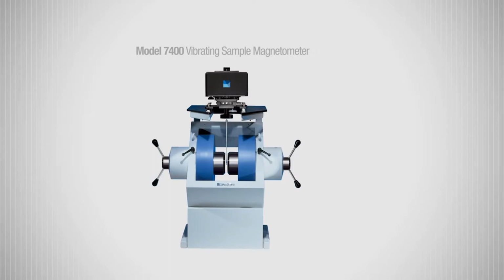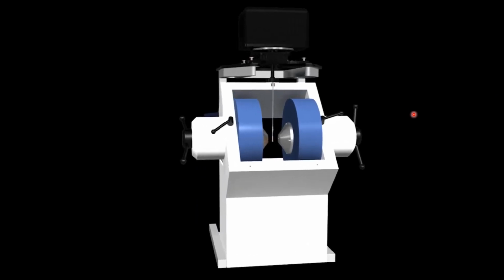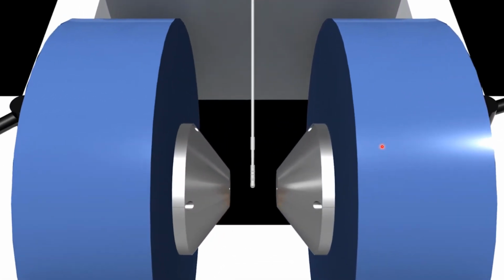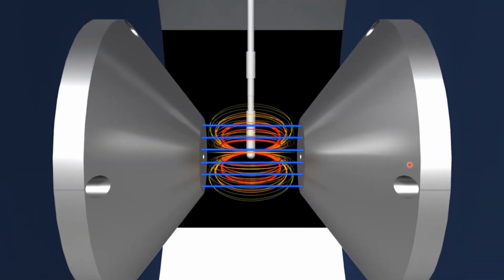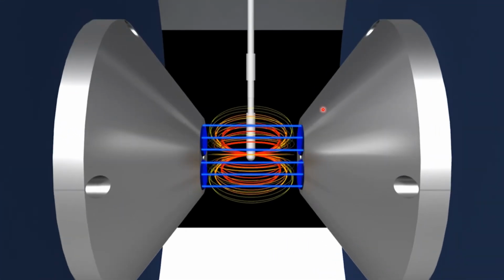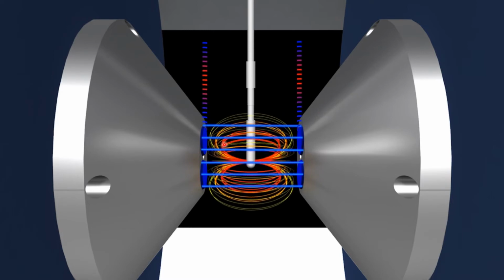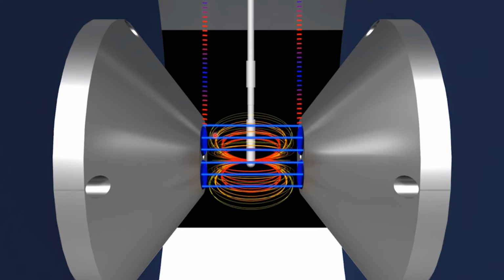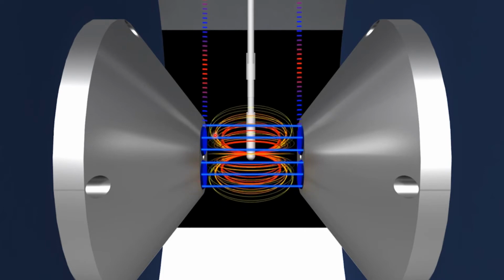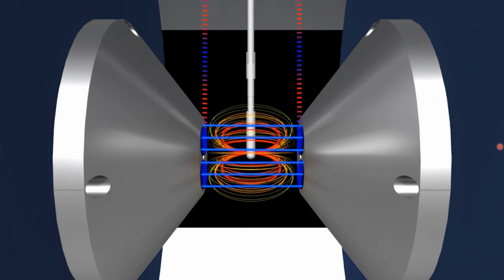The working principle of the vibrating sample magnetometer can now be described. When the sample is mounted inside the electromagnet pole pieces, it will get magnetized, and as it is magnetized, it will behave like a small magnet inside the system. And when this sample oscillates inside the pickup coils, it will generate a current pulse which is proportional to its magnetic moment, and that is how the magnetic properties of the system are measured by using VSM.